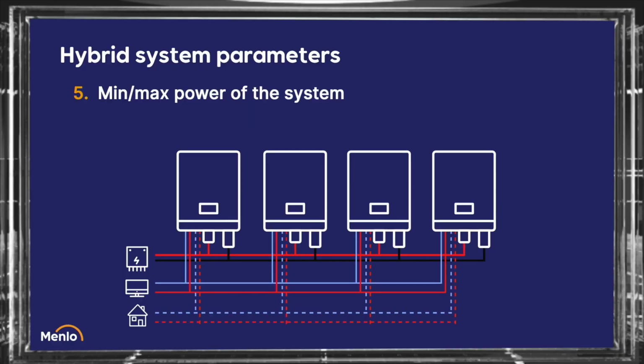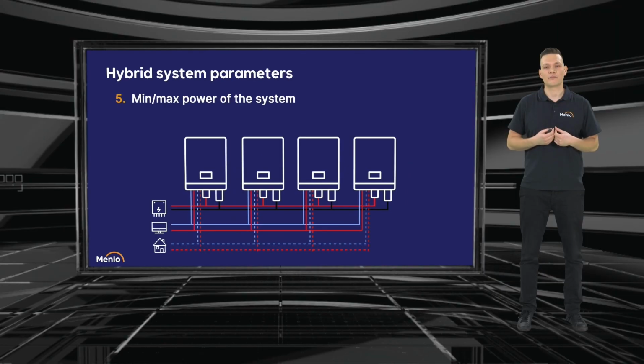Then we have minimum and maximum power of the system. The minimum would be, of course, the power of a single inverter. But the maximum is not only the maximum of one inverter, because inverters can be paralleled, so they can work together. It's also important to know, if you need a bigger installation, how they work together, and if you can connect, for example, the batteries and the loads together, or they need to be separate. If you plan a bigger installation, that's something to consider.